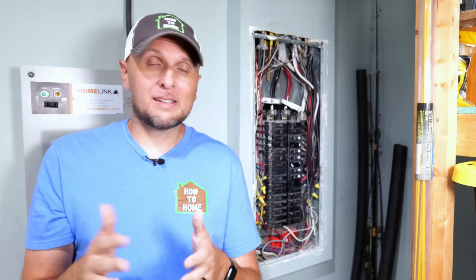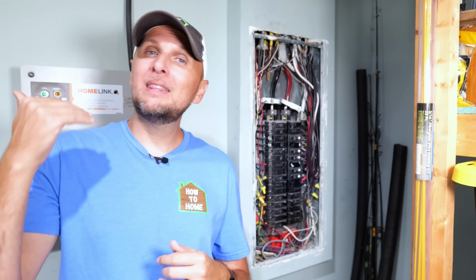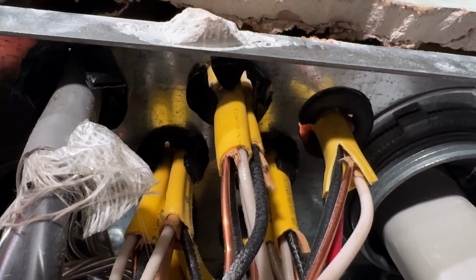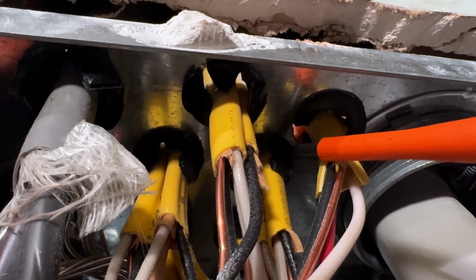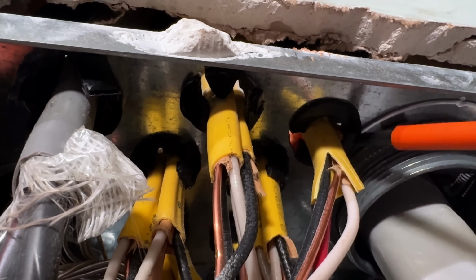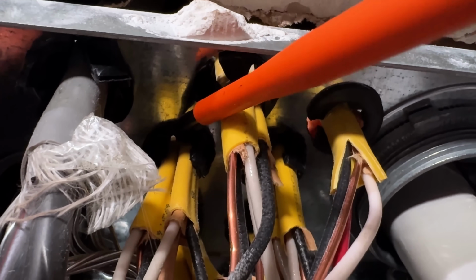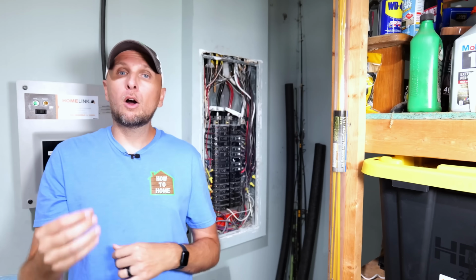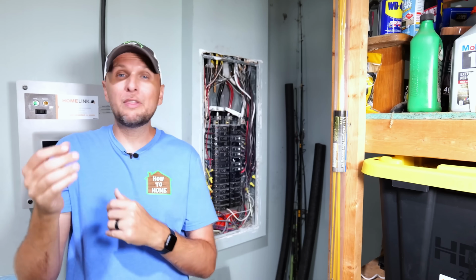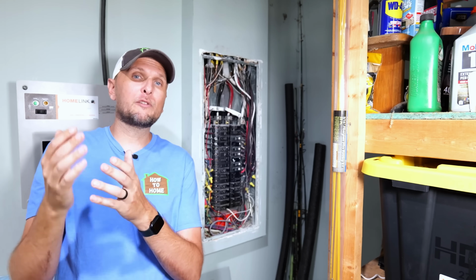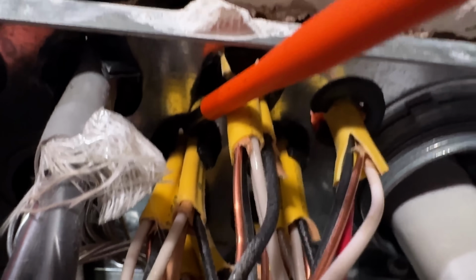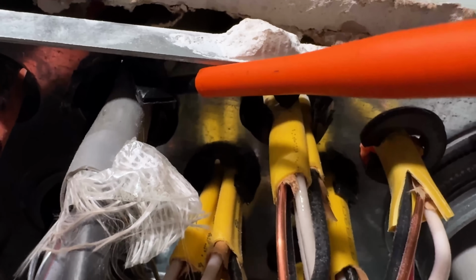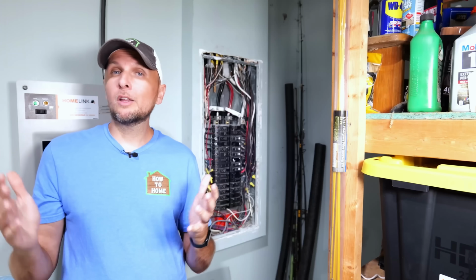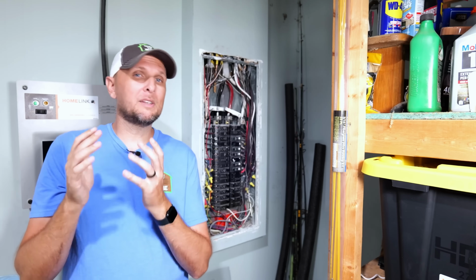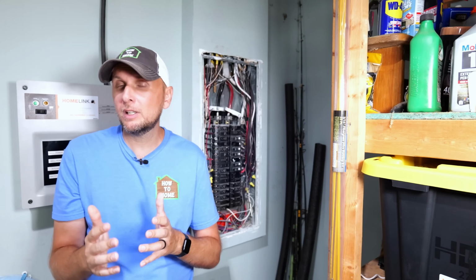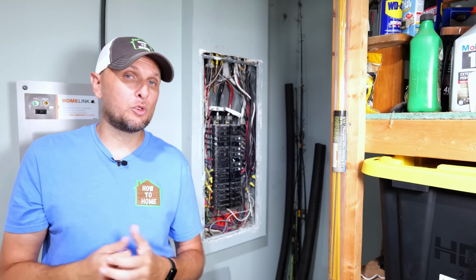But the fix for this, obviously, is going to be very easy. It's going to be the opposite of that. And that is to use a Romex connector or bushing for every single one of those knockouts where those wires are coming through. Now, there are different types of them. There are metal connectors that have screws, and these are very durable and they last for a very long time. There are also plastic snap-in ones, which I have in here on my panel, but regardless of which one you're using, they are all designed to protect the wiring insulation and to provide any necessary strain relief.